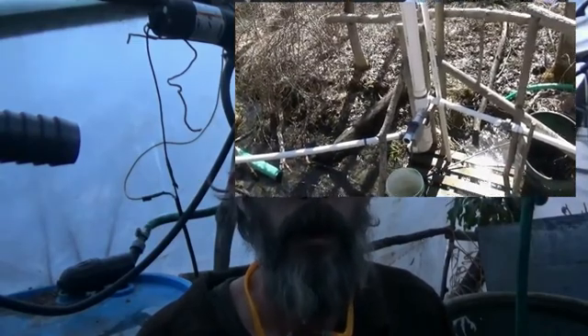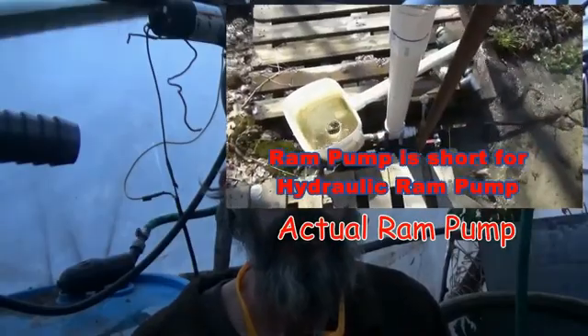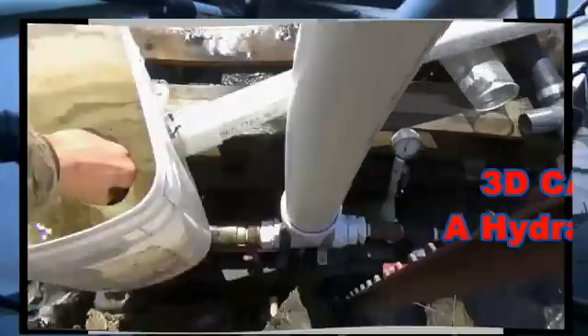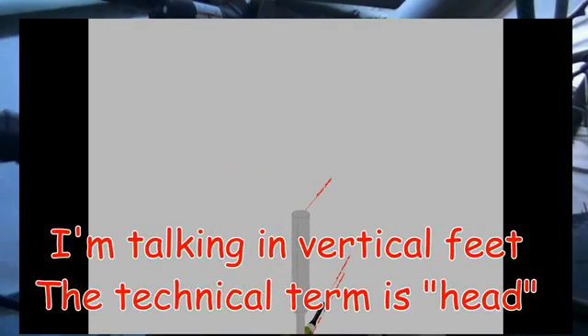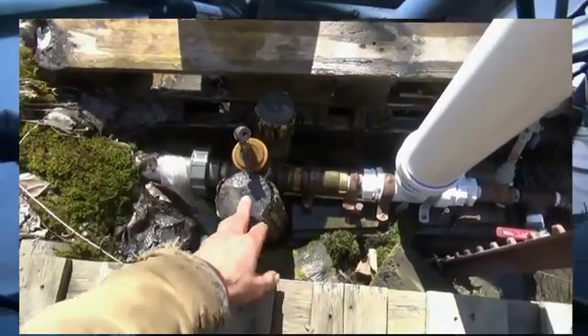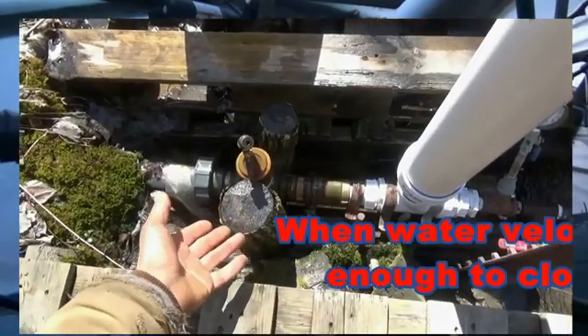A ram pump is a hydraulically operated pump. It uses a portion of the water that is falling from a water source to drive pressure in the pump. Some of that energy is transferred to build pressure in the pressure chamber, which delivers a small portion of the water to your destination. A ram pump will typically pump about ten times the fall distance, and usually delivers around ten to fifteen percent of the total volume throughput.